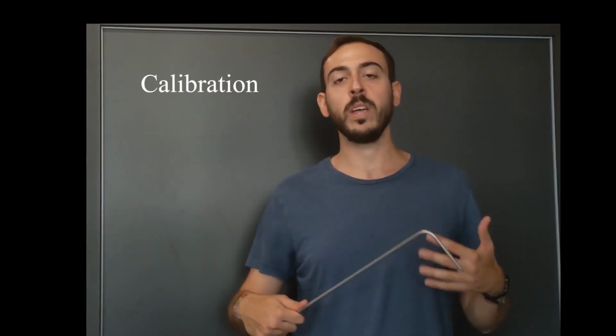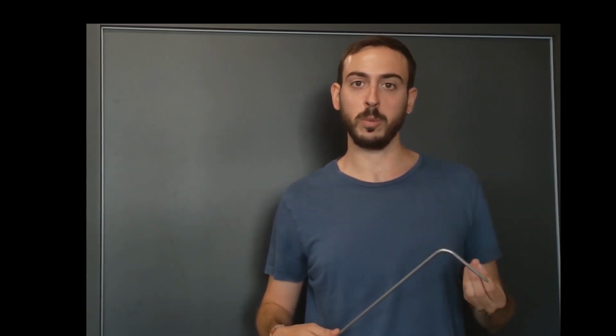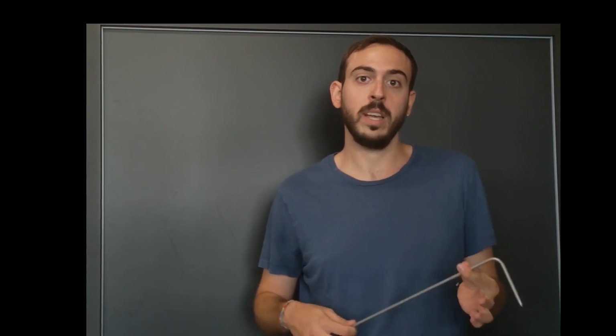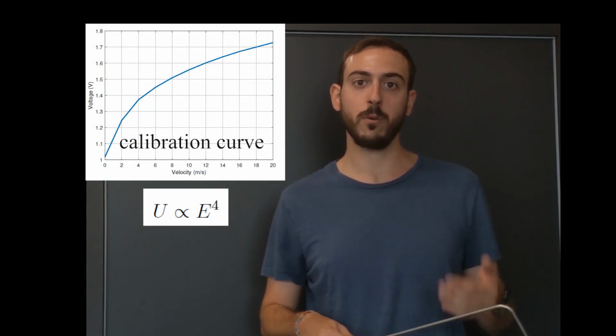Now, how do we calibrate this hot wire system? The system allows us to link the flow speed and the output voltage, but of course we need to calibrate it against a reference velocity sensor, which is usually a pitot tube. To this aim, during the calibration, the hot wire probe and the pitot tube are placed at the same streamwise location within the tunnel, and we can assign the output voltage given by the hot wire system to the velocity value measured by the pitot tube. These two quantities are usually related with a fourth-order polynomial.